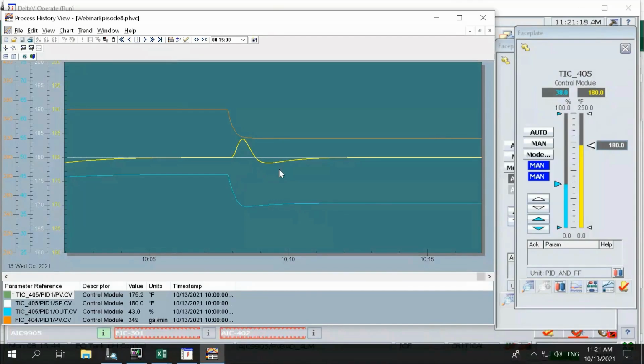I even say that for boilers, a lot of times we'll see a feed forward gain around 1, because a pound of steam is equal to a pound of water, and a lot of times it works. But I'm always more comfortable backing off the feed forward gain to maybe 0.8 or 0.7, leaving most of the job to the PID, the feedback controller. The feed forward will help you, but most of the job should be left to the feedback controller.